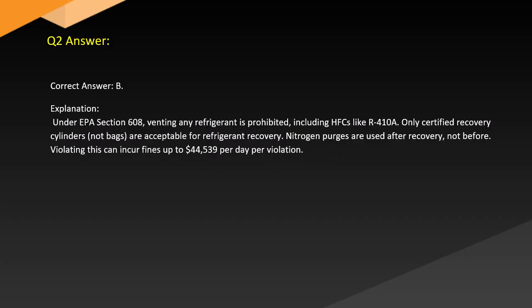Answer. Correct answer: B. Explanation. Under EPA Section 608, venting any refrigerant is prohibited, including HFCs like R-410A. Only certified recovery cylinders, not bags, are acceptable for refrigerant recovery. Nitrogen purges are used after recovery, not before. Violating this can incur fines up to $44,539 per day per violation.